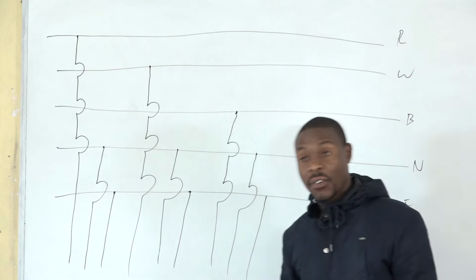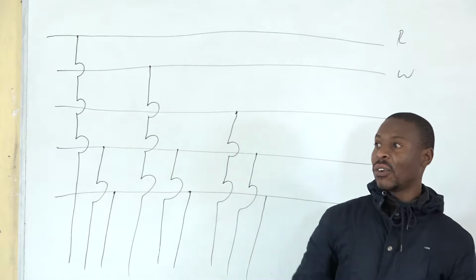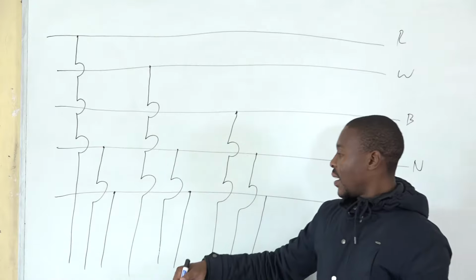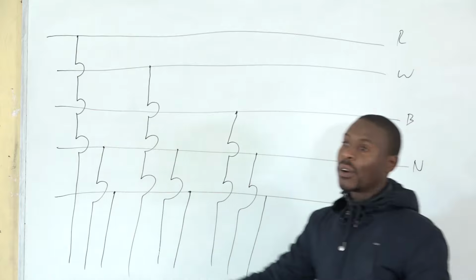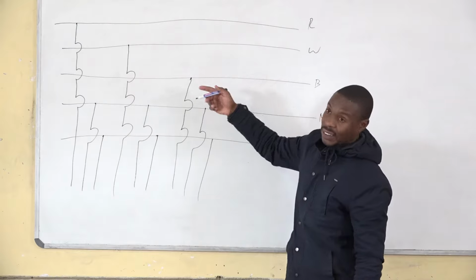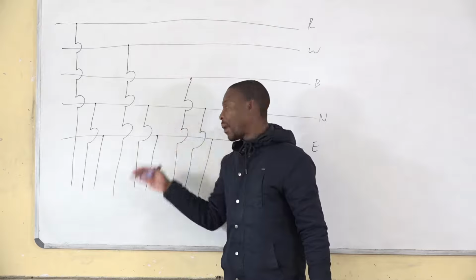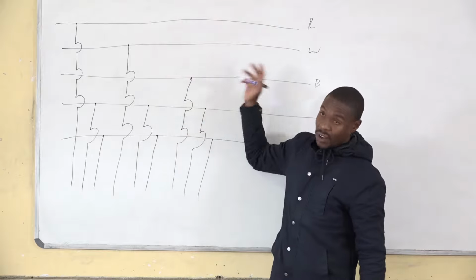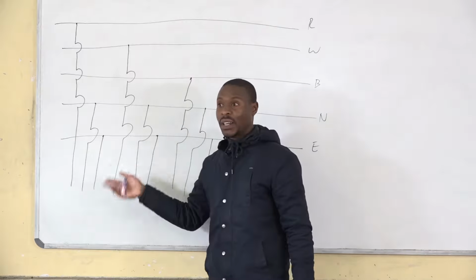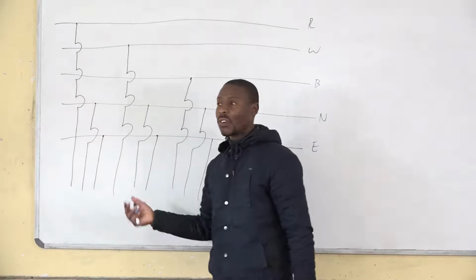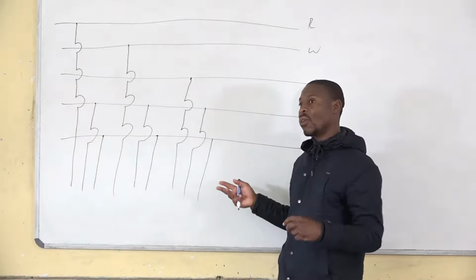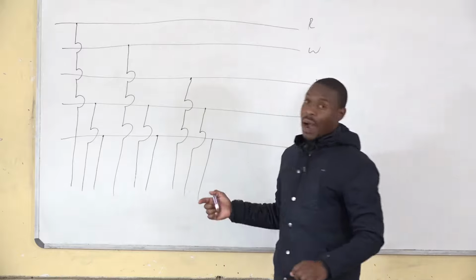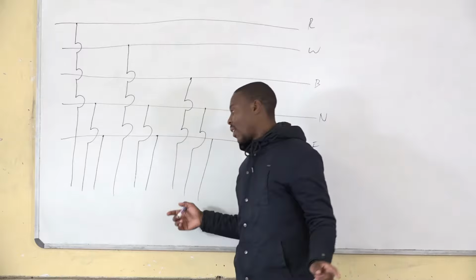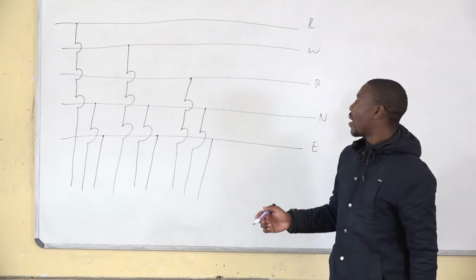So even if there's a fault, you will find that in this street they don't have electricity. It is because of what? That phase is dead or something went wrong. But the other two phases will still have electricity, but it will trip at some time because now the transformer is malfunctioning, pulling more power on these two phases compared to the other one. So that's the reason why we are balancing a load.